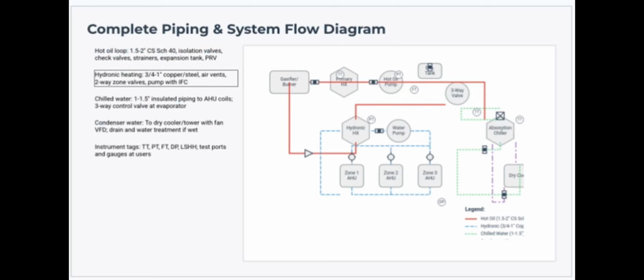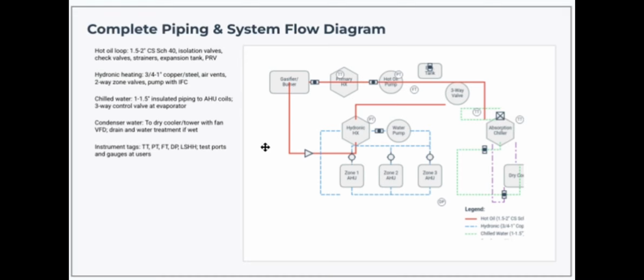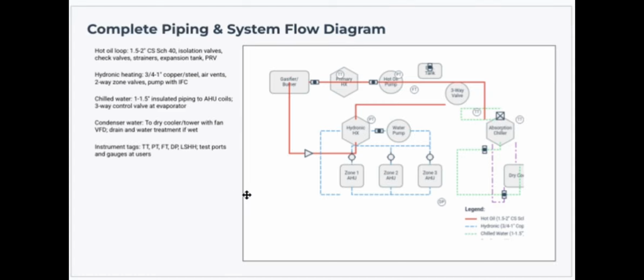The complete piping and system flow diagram: hot oil loop between 1.5 inch to 2 inch schedule 40, isolation valves, check valves, strainers, expansion tank, PRVs. For hydronic heating, the pipe size I will be using is 3/4 to 1 inch copper/steel, with air vents installed, two-way zone valves, pump with VFD. For chilled water I will be using 1 inch to 1.5 inch insulated piping to AHU coils, three-way control valve, and evaporator. Condenser water goes to dry cooler/tower with fan, VFD, drain, and water treatment if wet. Instrument tags, of course, test ports, and gauges at all users.